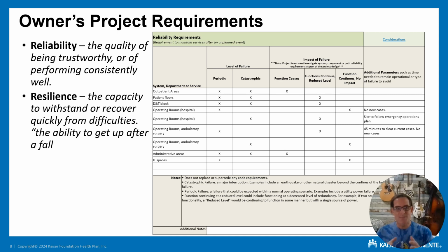Now, there are a few exceptions to that. In the operating room, we do want to maintain full capacity during an event, but it's for a limited period of time. If we have, say, a power outage in an operating room, in California at least, we need to have 2 sources of power in place to start surgery. So if one of those goes out, then we switch over to the second source, we finish out that surgery, we finish out that case, and then we stop. We cannot start a new surgery because we don't have 2 sources of power in place.